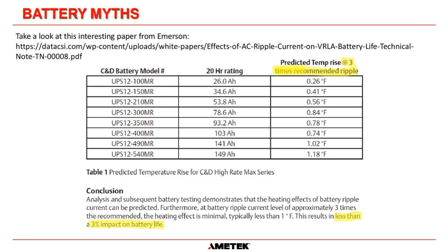Another battery myth is that the worst thing you can do is overcharge a battery. Actually, the worst thing you can do is undercharge a battery. Prolonged undercharging causes excessive sulfation of the plates, and that is how you kill a lead acid battery. It will eventually lead to irreversible loss of capacity because the sulfation turns into crystals, the crystals harden, and it stops the transfer of power between the positive and the negative plates. And if you leave it too long, those crystals are so hard that even an equalized charge won't get rid of them.